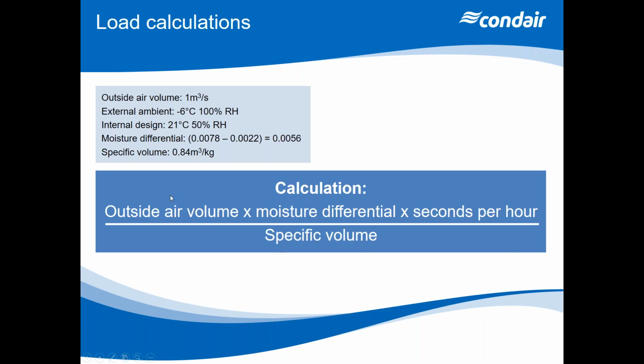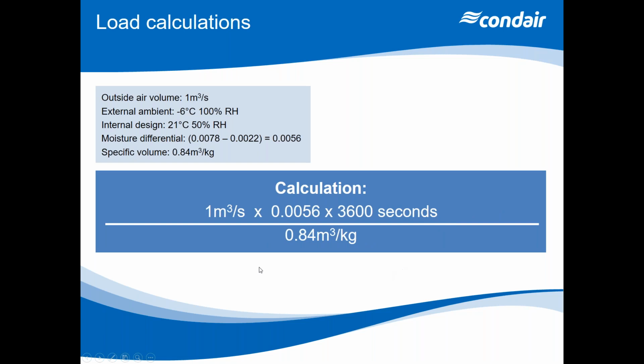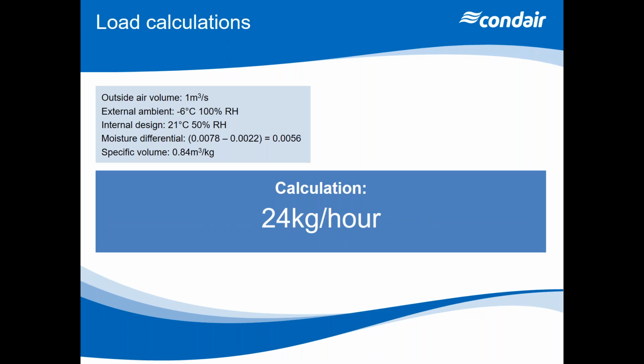So our calculation is pretty straightforward. We take the outside air volume, meters cubed per second. We multiply that by the moisture difference in kilograms per kilogram of dry air. Then we multiply that by seconds per hour, and then we divide it by the specific volume. So here we go: 1 meter cubed per second times 0.0056 kilograms per kilogram times 3,600, because we've gone from meters cubed per second to kilograms per hour, and we divide that by 0.84. This gives us a pretty good rule of thumb, because the answer is just over 24 kilos an hour.